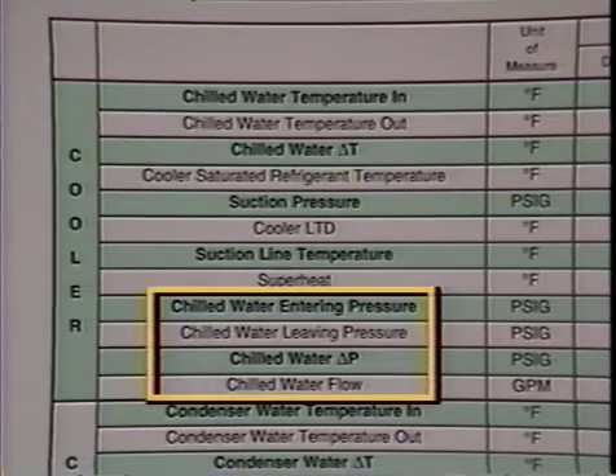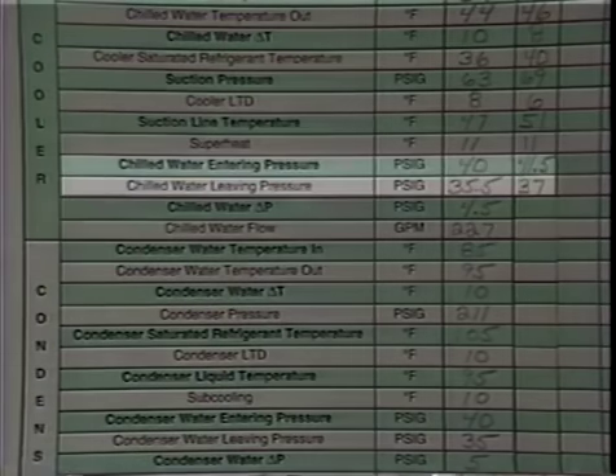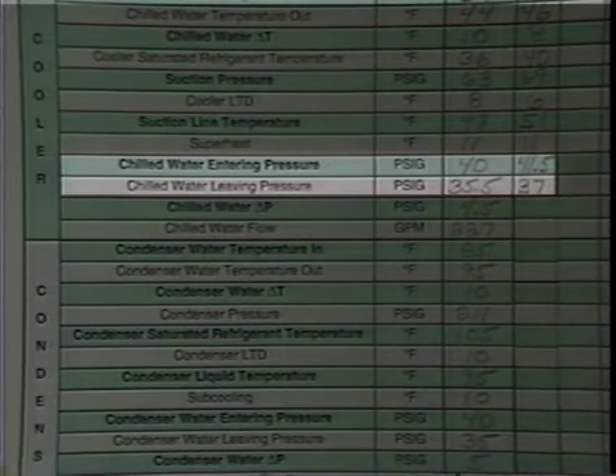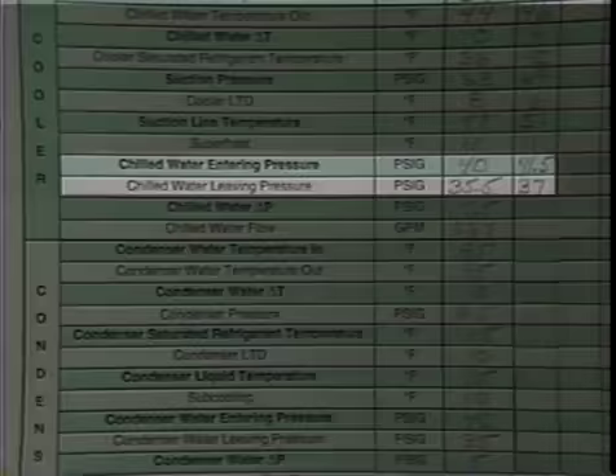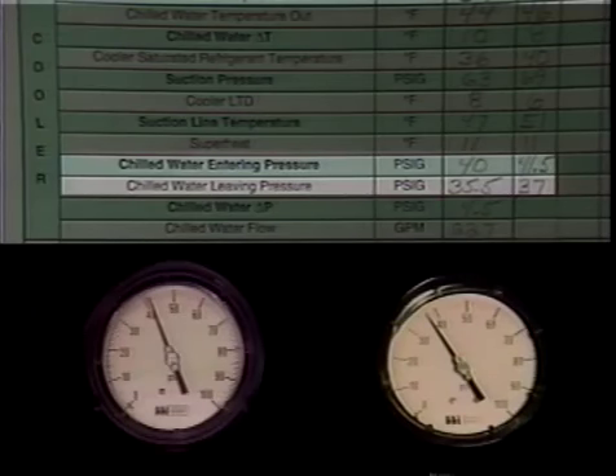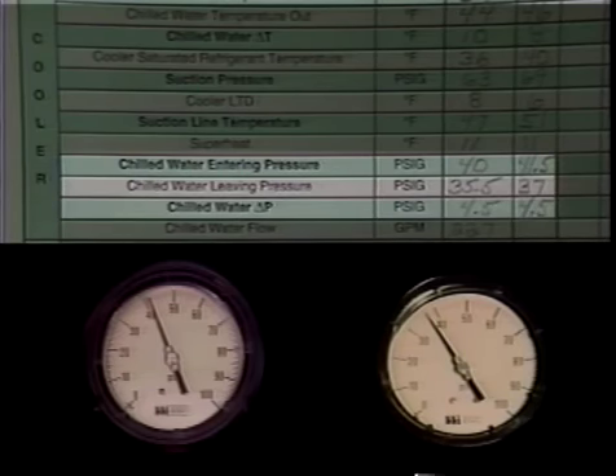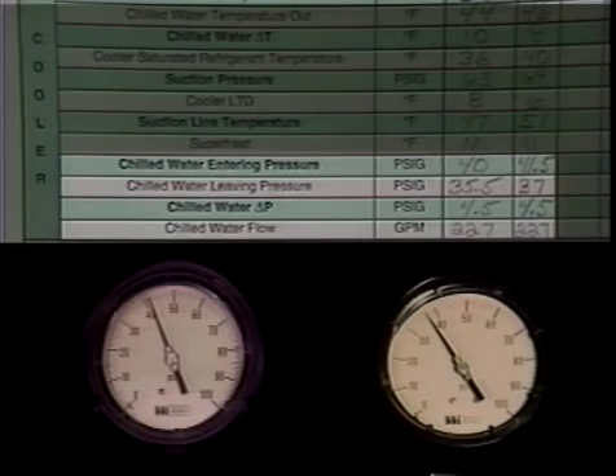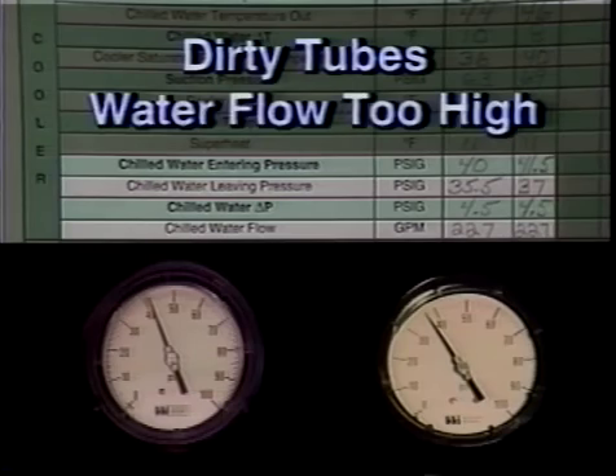Chilled water flow. Space on the log sheet is provided to record the entering and leaving water pressures. The same gauge should be used to take both readings to ensure accuracy. The difference between the two readings indicates pressure drop, or delta P. It can then be compared to the design pressure drop to determine GPM. If a greater than design pressure drop is recorded, there's a possibility that the tubes are either dirty or the flow is too high.